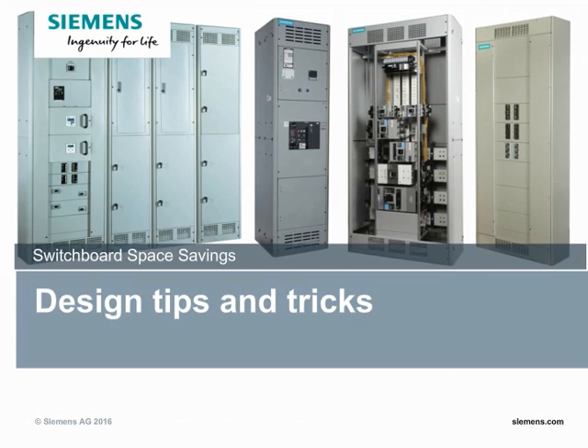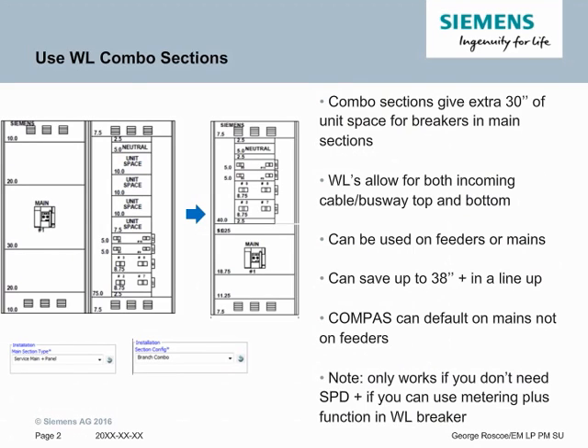Today's topic will be talking about switchboard space savings and design tips and tricks to get there. The WL combo section is a great way to save space. A WL combo section is a 38-inch wide section that combines a WL breaker, 2000 amps and below, with 30 inches of unit space for group mounted devices. This section design can be used as a feeder or a main section. It can also be used with busway or cable with a WL breaker, incoming or outgoing.